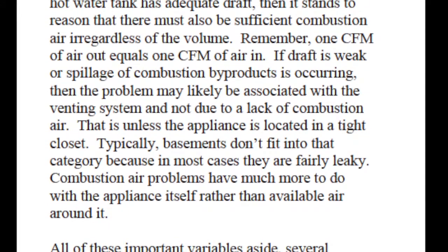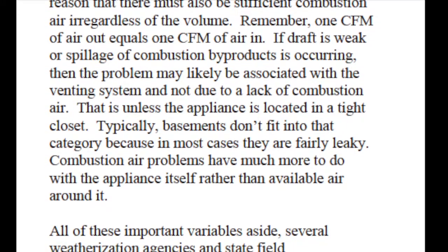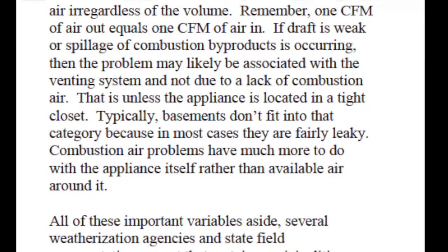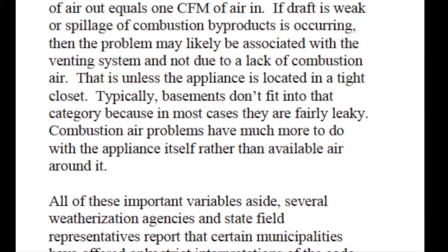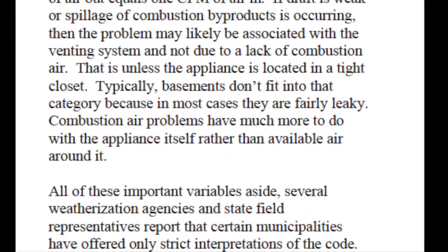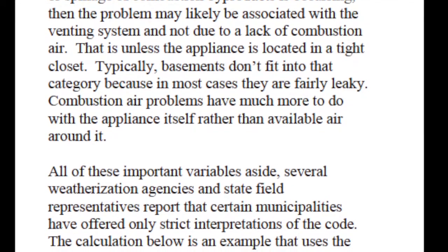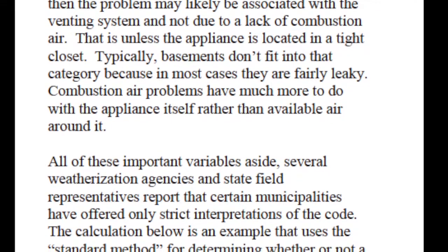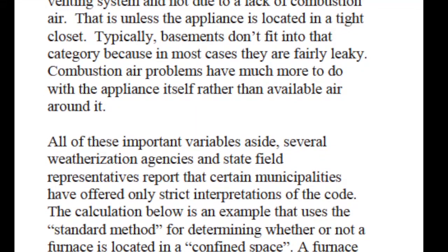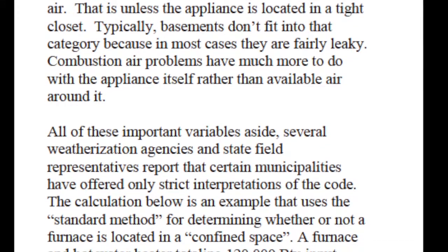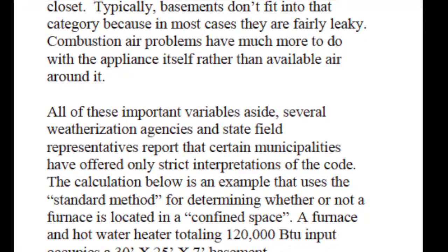If draft is weak or spillage of combustion byproducts is occurring, then the problem may likely be associated with the venting system and not due to a lack of combustion air. That is, unless the appliance is located in a tight closet. Typically, basements don't fit into that category because in most cases they are fairly leaky. Combustion air problems have much more to do with the appliance itself rather than available air around it. All of these important variables aside, several weatherization agencies and state field representatives report that certain municipalities have offered only strict interpretations of the code.